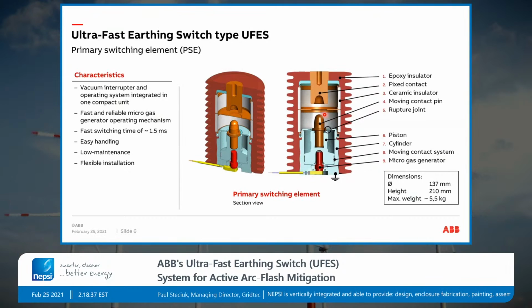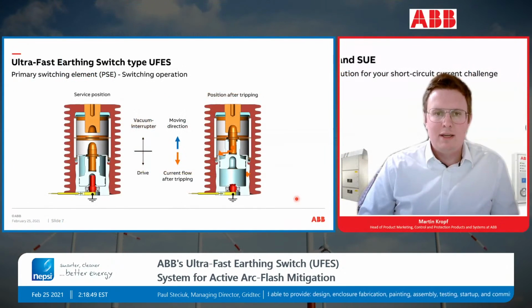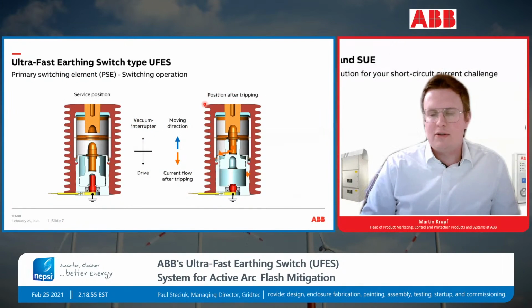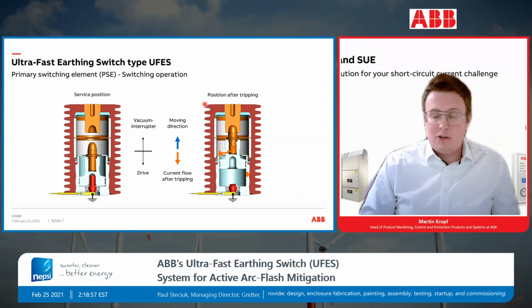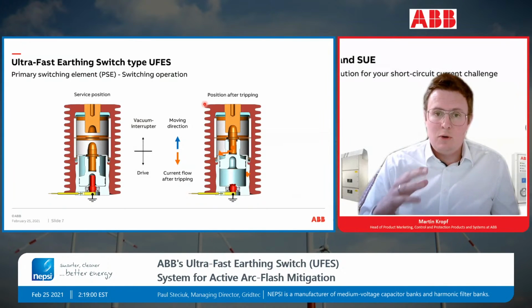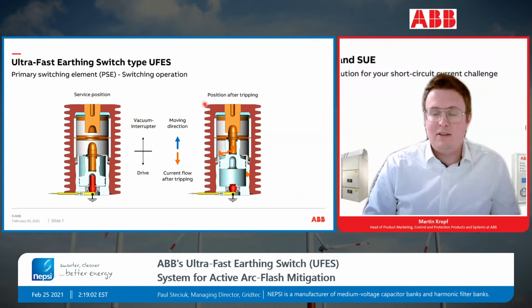You have some figures here on the size of this primary switching element. Closing takes around 1.5 milliseconds, and then the thing is closed, and it looks like this on the right-hand side. So after tripping, it's closed and we have a solid connection to ground. It's a one-shot device, so the idea is you replace this once it's earthed.